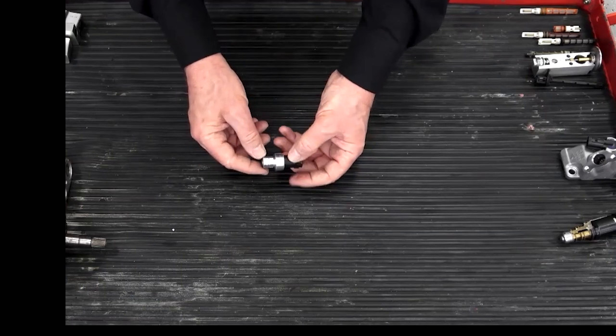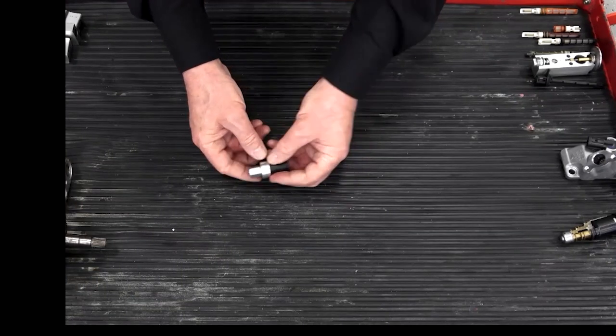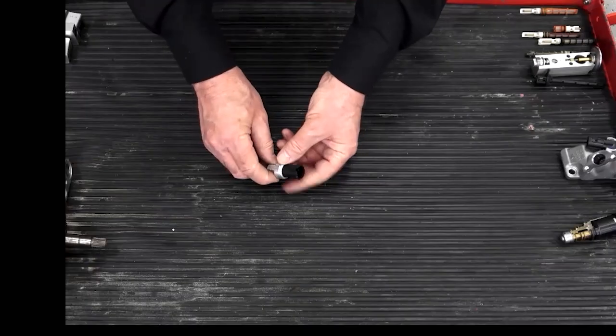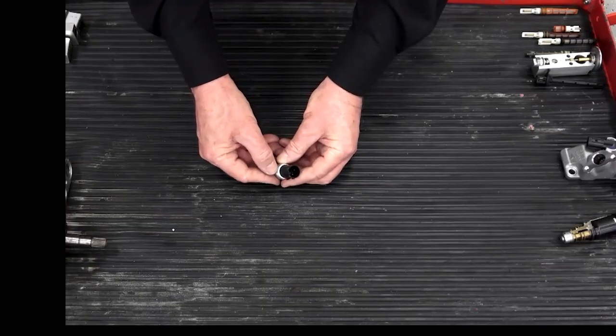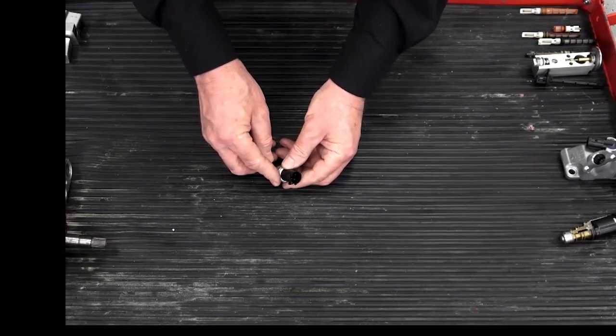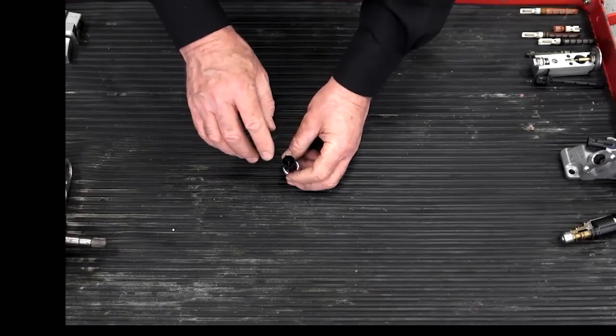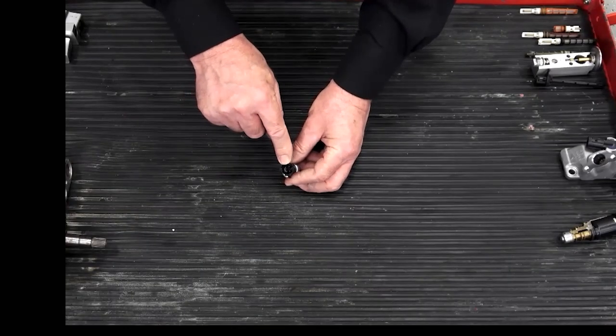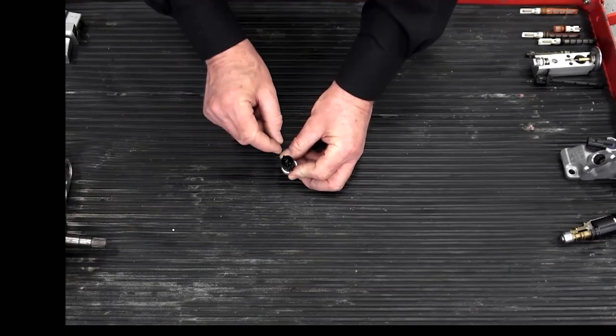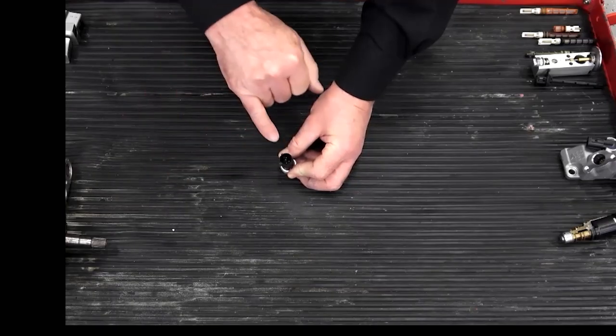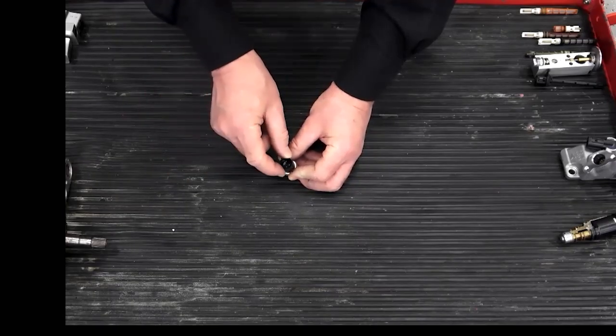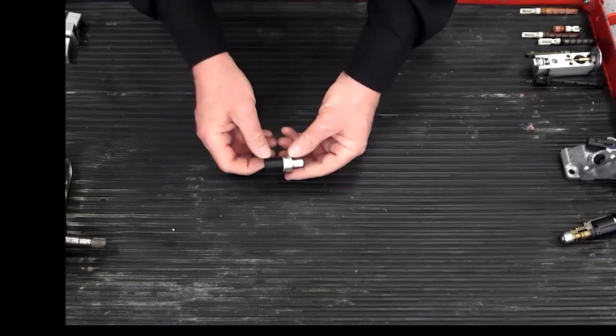undetected leak. They can leak where they screw onto the line. They can leak where there's an O-ring in here where the aluminum is rolled over on it, joining the plastic to the metal. And the real sneaker is I have seen a leak where the terminals come through the plastic. Sometimes if you disconnect the connector and look inside, you might see kind of an oil stain in here. You can get a leak through the terminals as well.